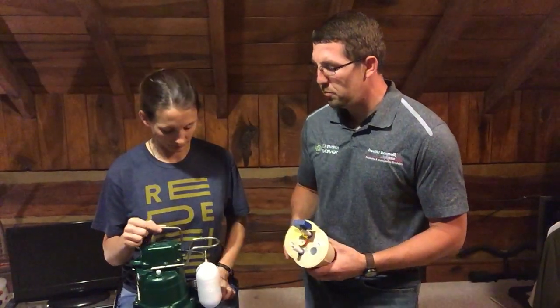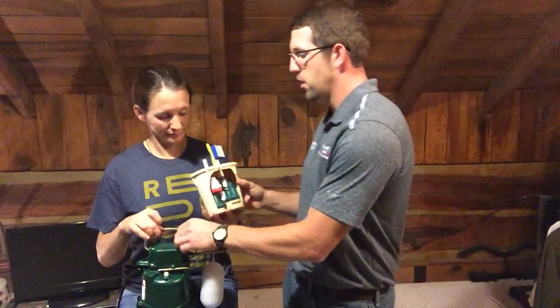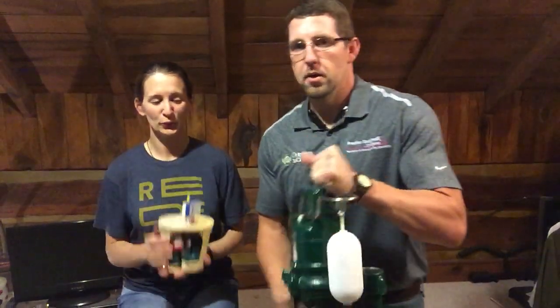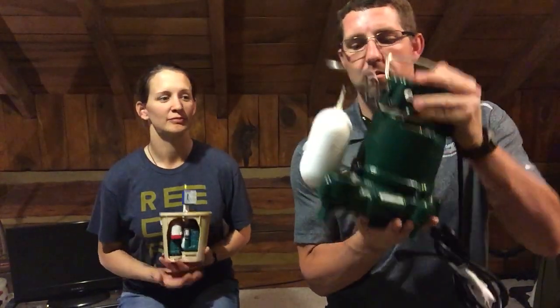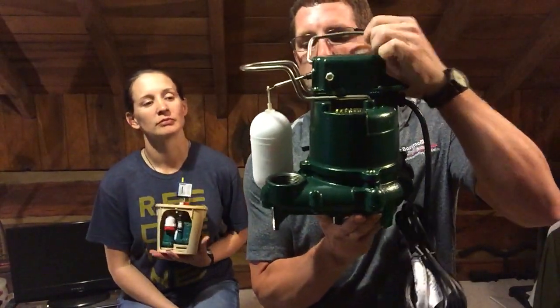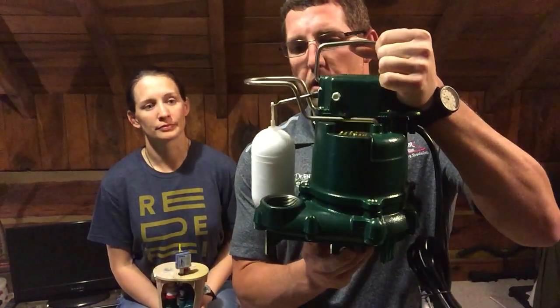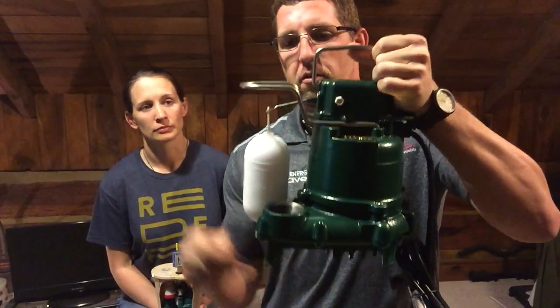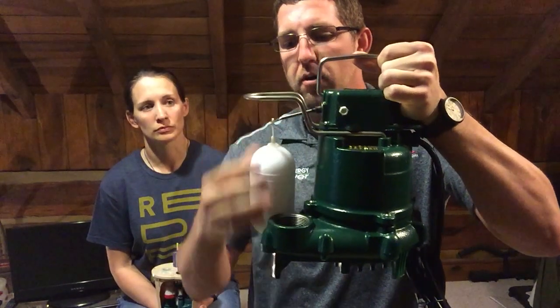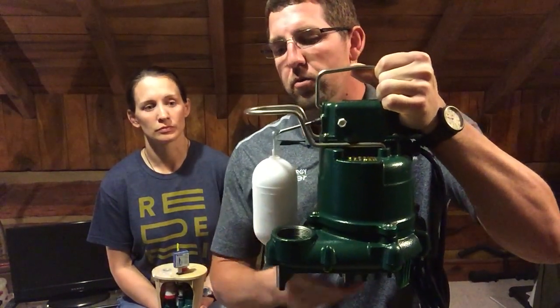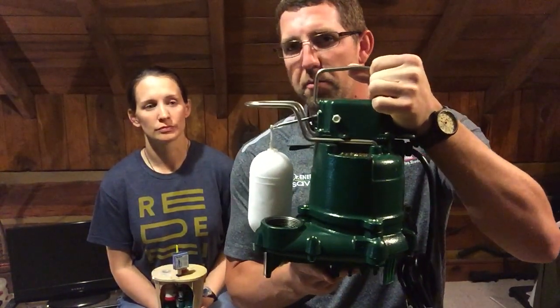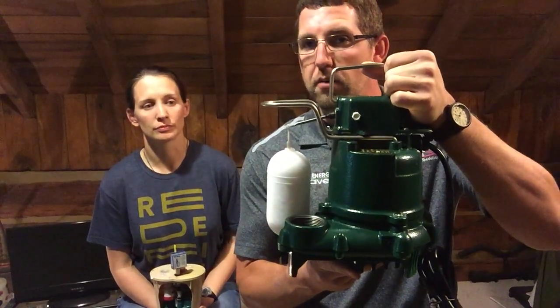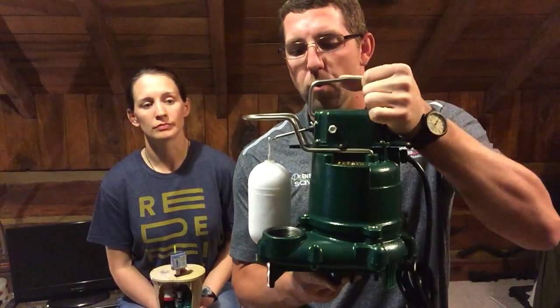But what's important on these pumps - let me trade you my little model for the pump. So this is a Zoeller M53, a 1/3 horsepower pump. What makes this really a great pump is not just the switch that's right here - the float is a solid float, so if it rubs up against something or gets a hole in it, it's not going to fill full of water and stop working for you.